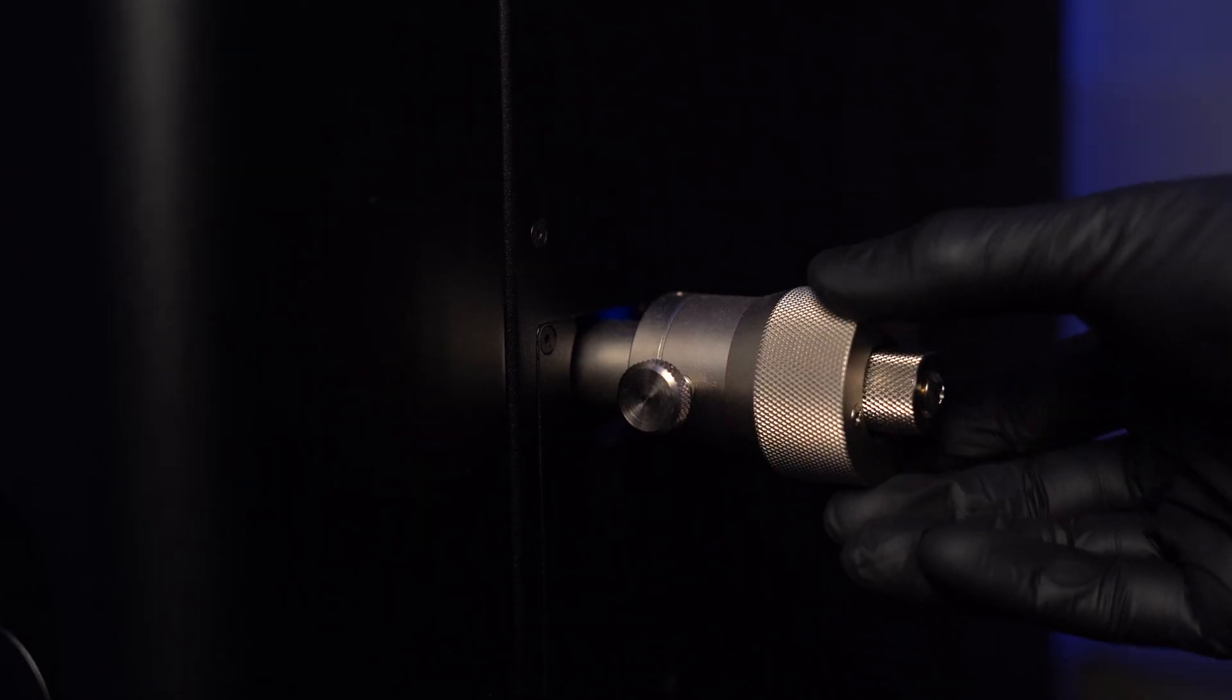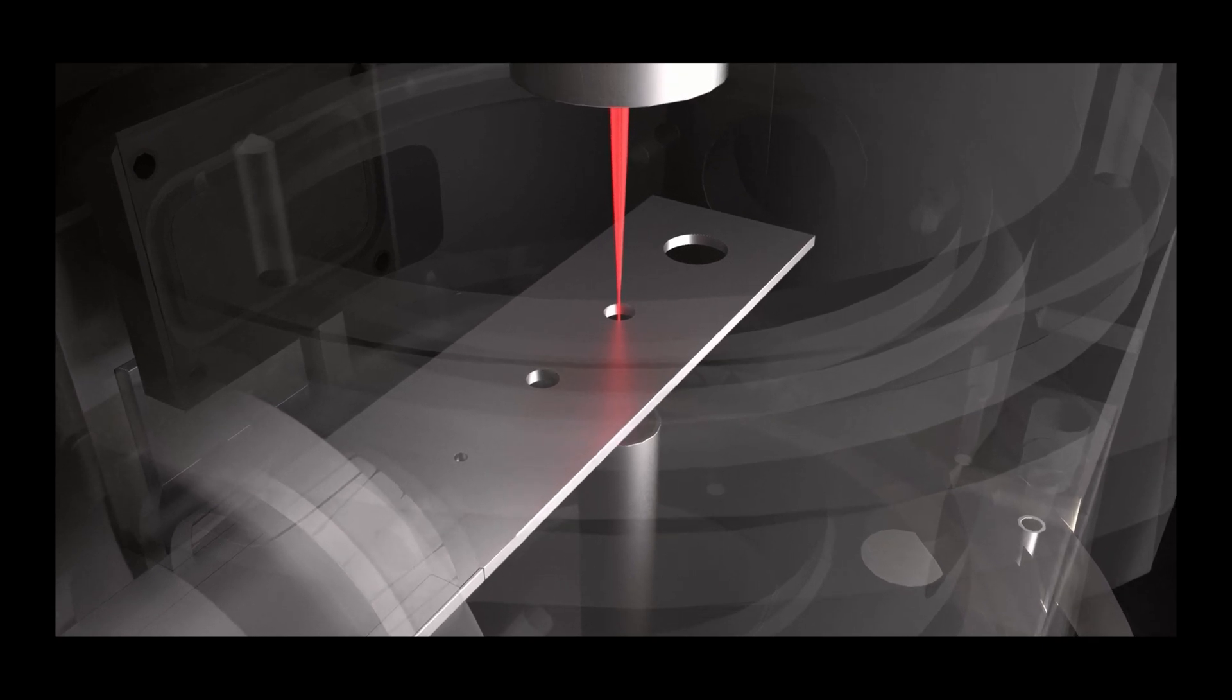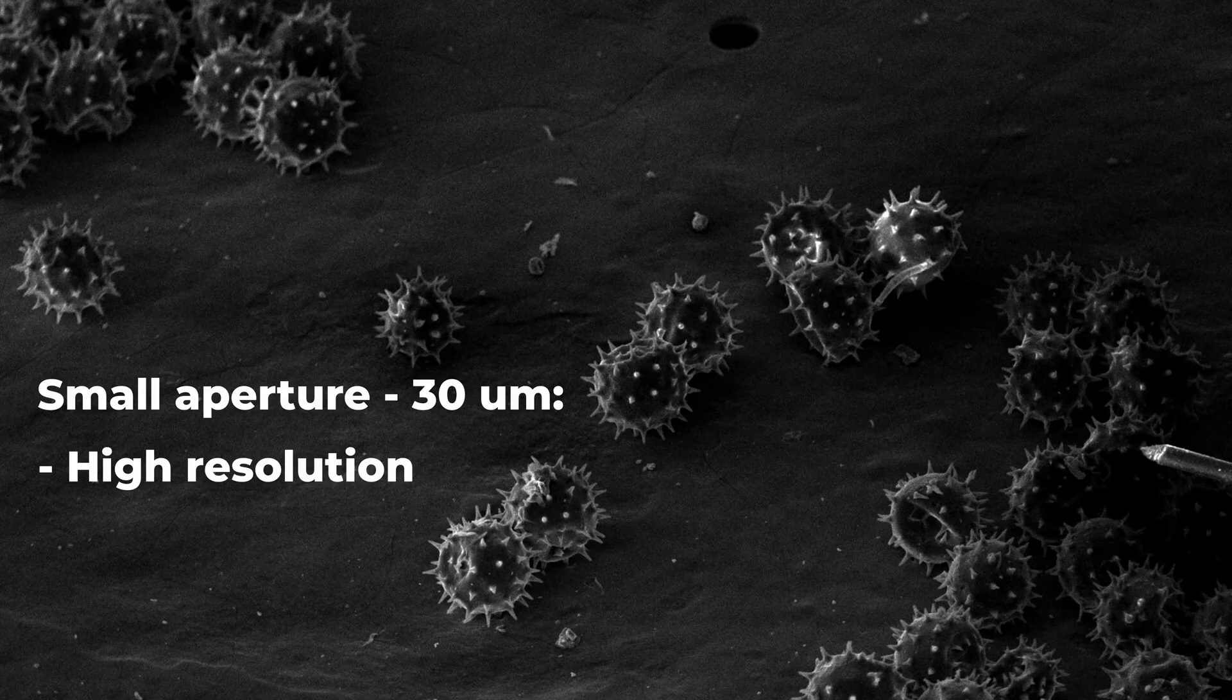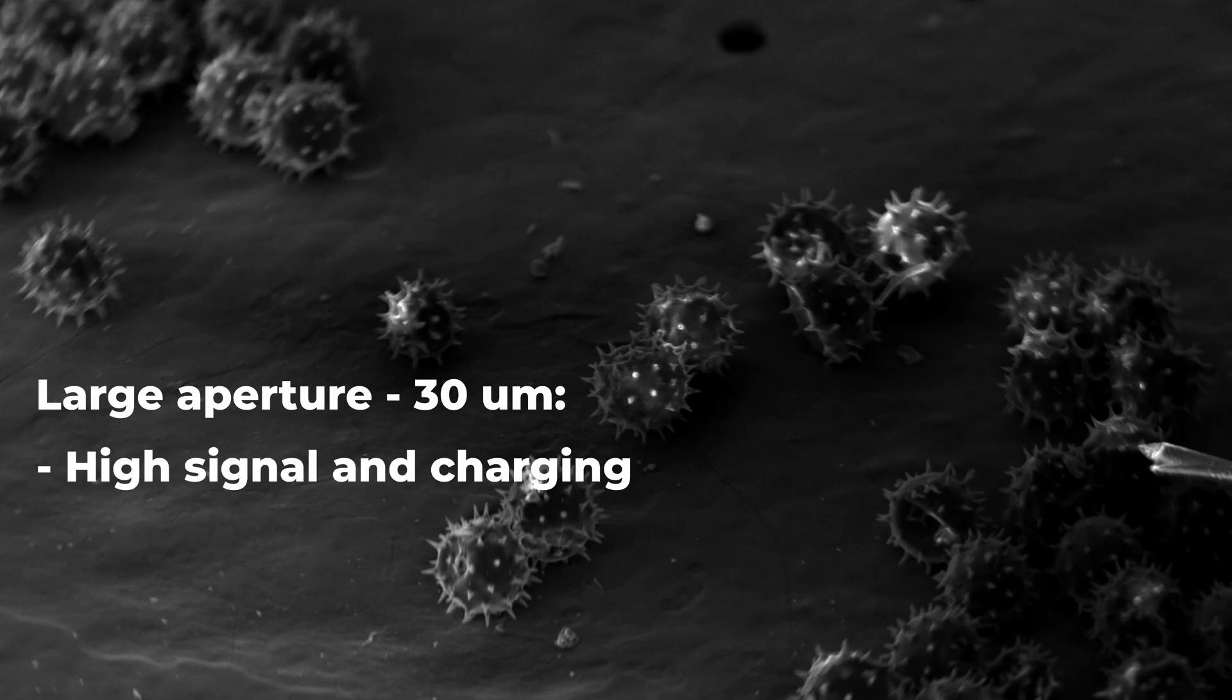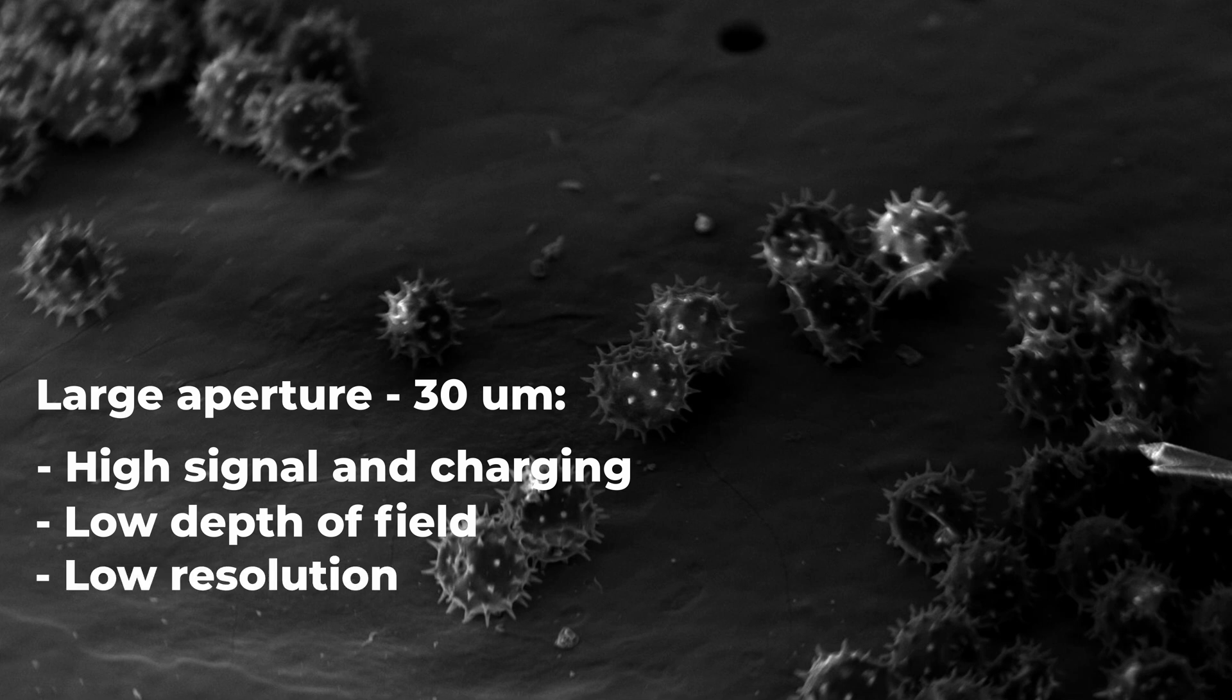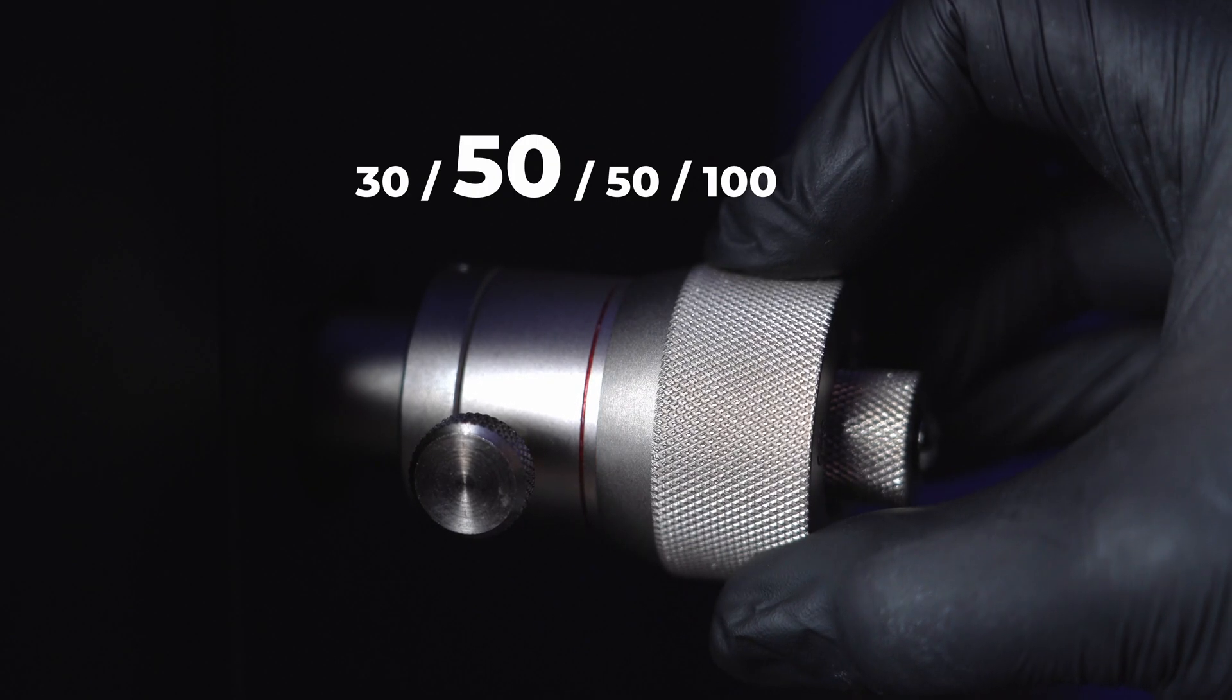On the right side there is an aperture knob with different apertures. We can control beam convergence angle and beam diameter. Small aperture, higher resolution, greater depth of field but lower signal because you're cutting off part of the electron beam. Large aperture, high signal but less depth of field and lower resolution. The mid-range of 50 microns is a great starting point.